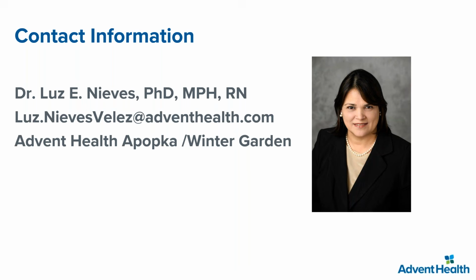Okay, the next question is by Christy Walker. Is there a special process that needs to be followed or testing that needs to be completed if a sterilizer or washer is down for repair prior to using it again? Yes, that's a very good question, and that is a question that CMS or Joint Commission is going to ask you. If you have a sterilizer that failed, for instance, to change the biological indicator, the strips or the chemical strips, or failed any of the process, that needs to be placed down. You need to call the biomed. The biomed needs to do a revision, do a run test on that sterilizer. If the sterilizer needs to be fixed, it's going to be placed down, and you need to run 3 cycles, okay? 3 cycles that have to be negative in order to put that sterilizer to work again.